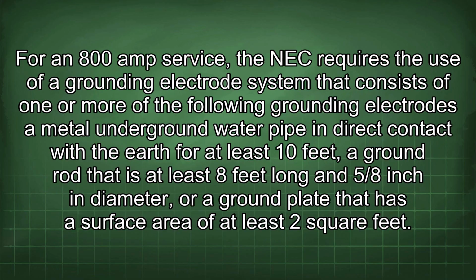For an 800 amp service, the NEC requires the use of a grounding electrode system that consists of one or more of the following grounding electrodes: a metal underground water pipe in direct contact with the earth for at least 10 feet, a ground rod that is at least 8 feet long and 5/8 inch in diameter, or a ground plate that has a surface area of at least 2 square feet.